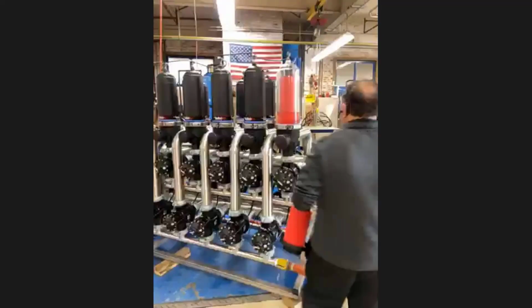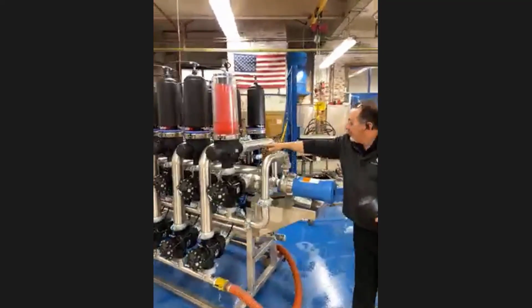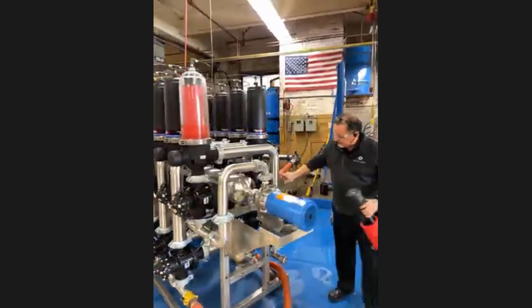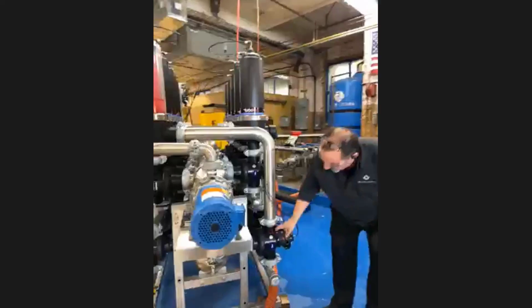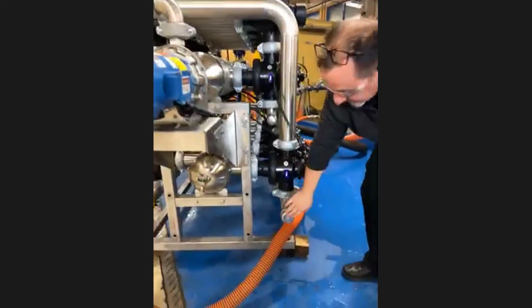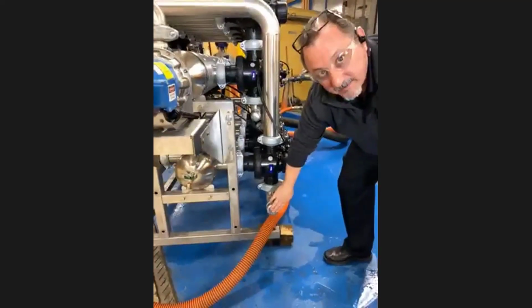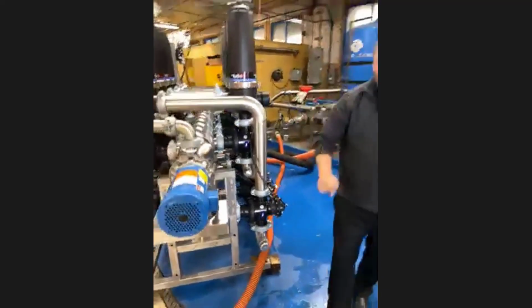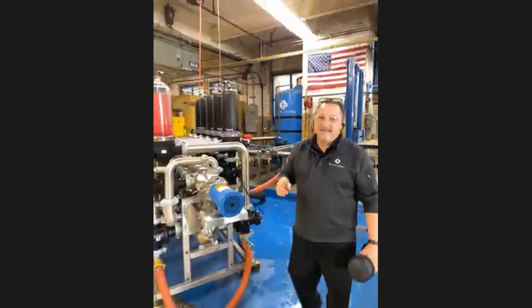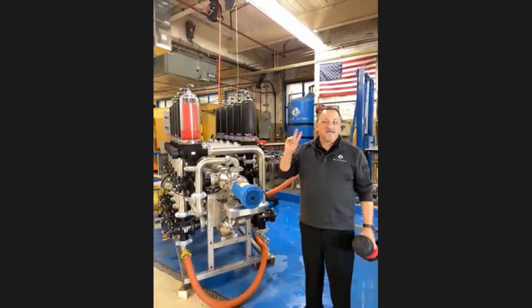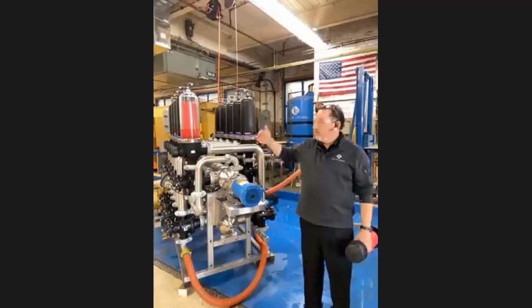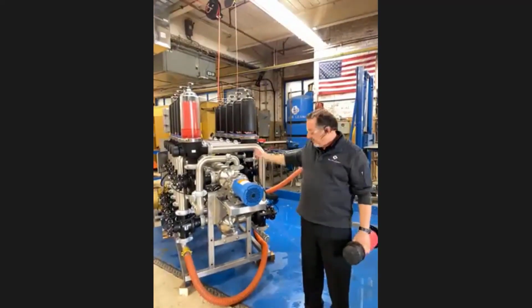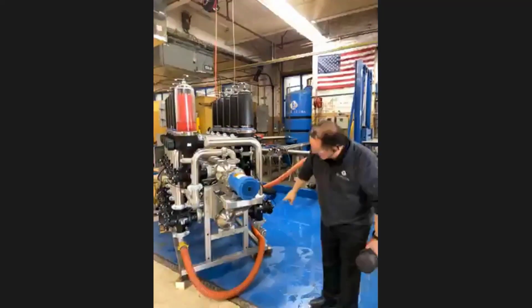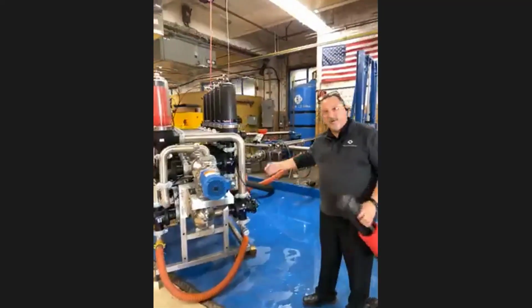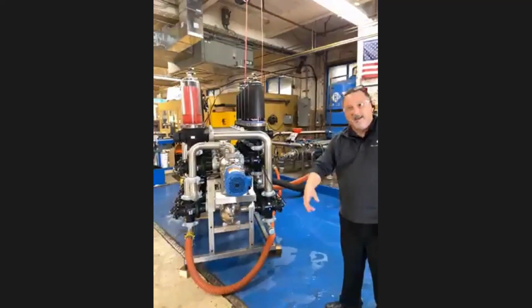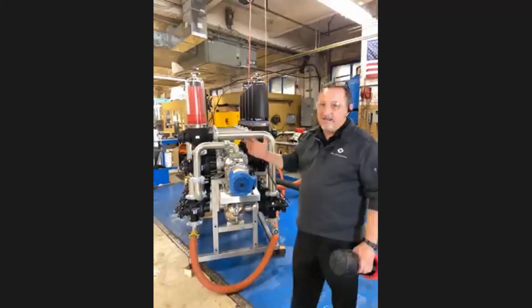And then what happens is that water goes back out, the dirty water back this way, down through. Remember, this valve was an L. Now it's straight across like the other valve into the backflush manifold, which is right here. All it is a 2-inch backflush manifold. On the 10,000 gallon per minute system, all it is a 2-inch backflush manifold because you're only backflushing a certain amount of pods each time. Now, these backflush manifolds don't come together, so you have to pipe them together to a drain. Typically, a 2-inch, 3-inch drain is going to be perfectly fine.